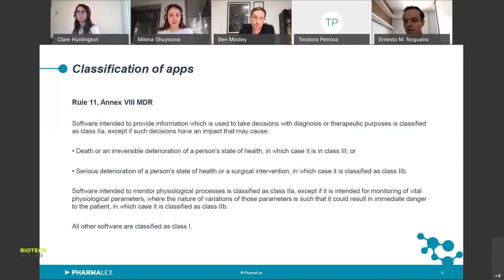This is Rule 11. And this tells us that if the software is intended to provide information that's then used for decisions with diagnosis or therapeutic purposes, it should be a 2A, unless it has an impact that could result in a death or irreversible deterioration. That would be considered a class 3, so the highest risk of medical devices that we have. If that software could potentially lead to a serious deterioration of a person's health or a surgical intervention, this would be a class 2B medical device. If it's monitoring physiological processes, it's a 2A, unless it's a vital physiological parameter which could result in immediate danger. That is then a class 2B, and all other software is class 1.